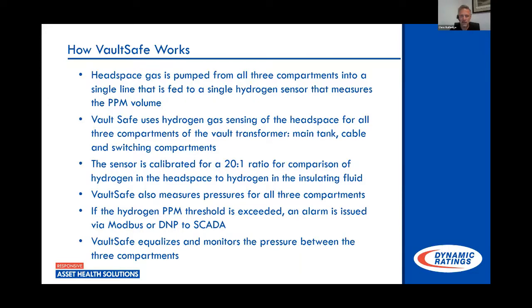So when you're looking at hydrogen in oil, and if you've done much DGA sampling, you'll see a lot of samples where you may have methane, or ethylene is a great example because it's a very sticky gas. It stays in the oil for a long time, so its solubility rate's much higher. Whereas the solubility rate for hydrogen runs about 5%.